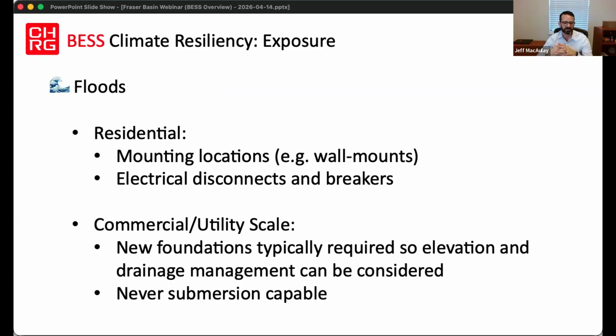Mounting locations exist, so virtually every resi option we have has wall mounts. I think it's important if you're in certain areas, close to the Bow River in Calgary, or in a floodplain in Richmond or wherever, wall mounts are important. If you're buying yourself 3 or 4 feet off the ground, you're massively reducing the risk that the battery is underwater. Primarily, water is going to cause damage and not a major safety issue because of our electrical codes that exist.